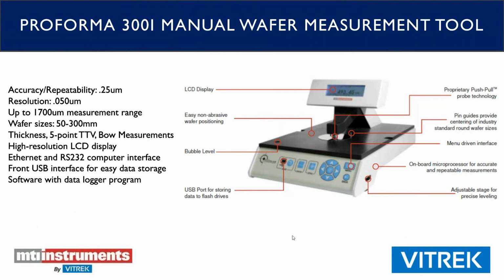It does have a USB port on the front, so you can store and log your data for your thickness variation, and there's also a bow measurement that you can do with the Proforma 300i. All of our technology, both the 300i and the 300 ISA, give you an accuracy of 1/4 of a micron, and it gives you a 50 nanometer resolution. So this can be used for wafers with a 1700 micron or 1.7 millimeter measurement range. So the probes are adjustable. So if you do have a thicker wafer, you can adjust it, calibrate it accordingly, and get your measurements.